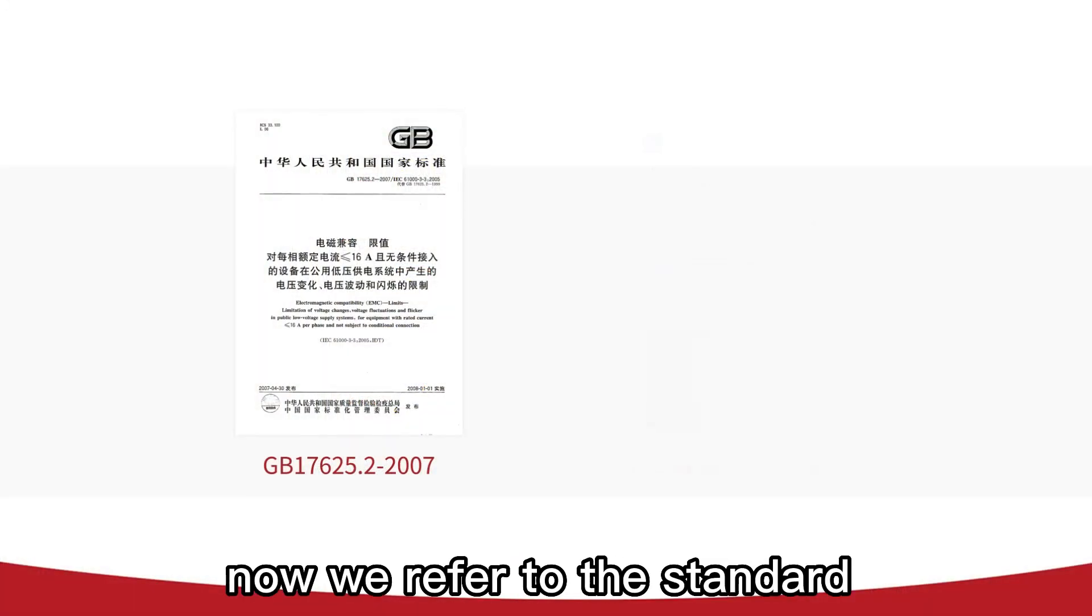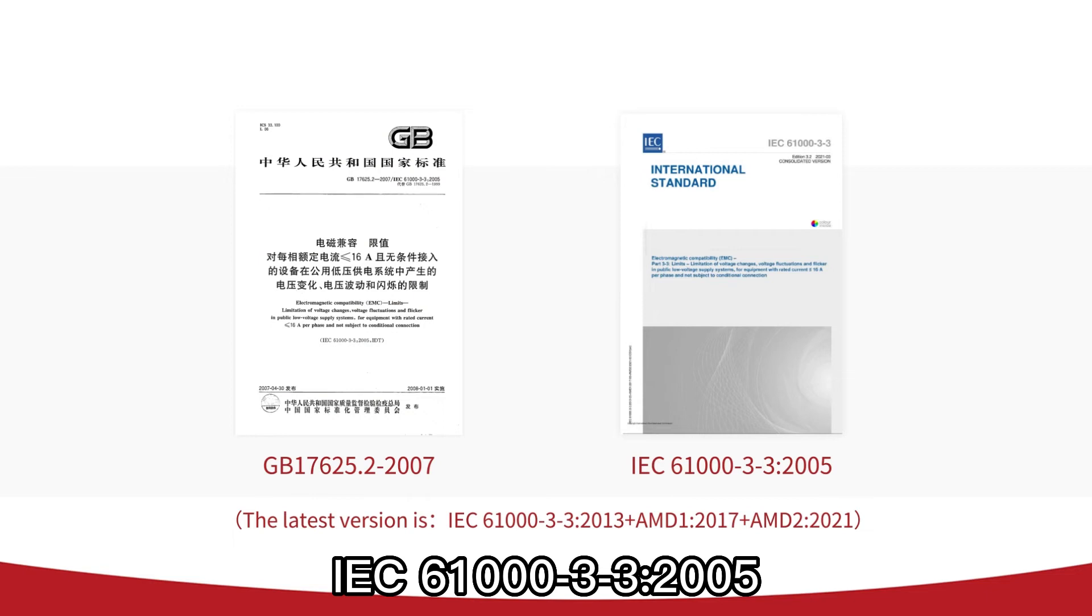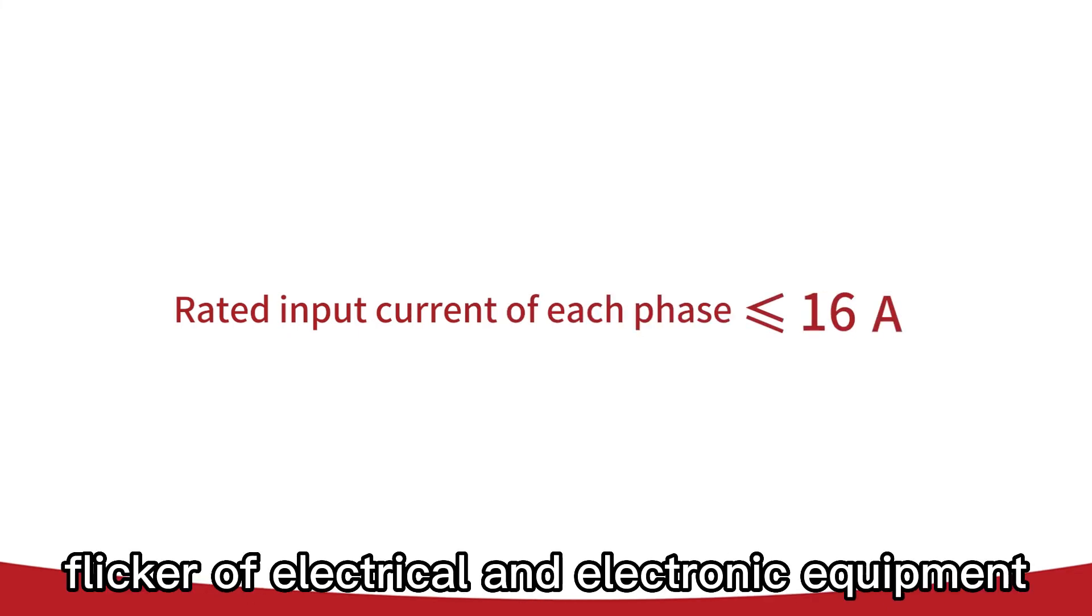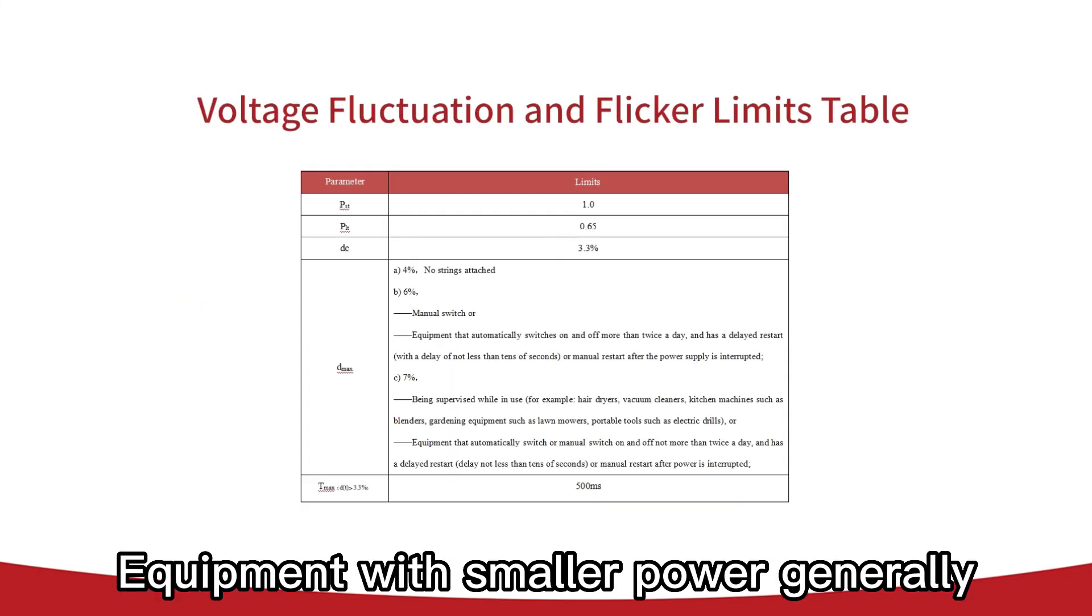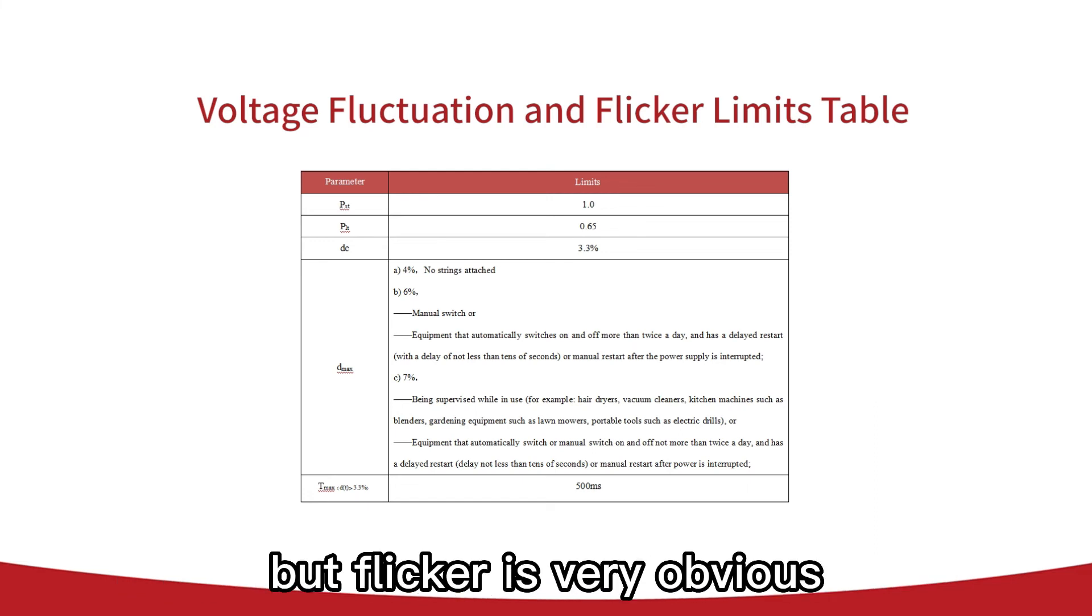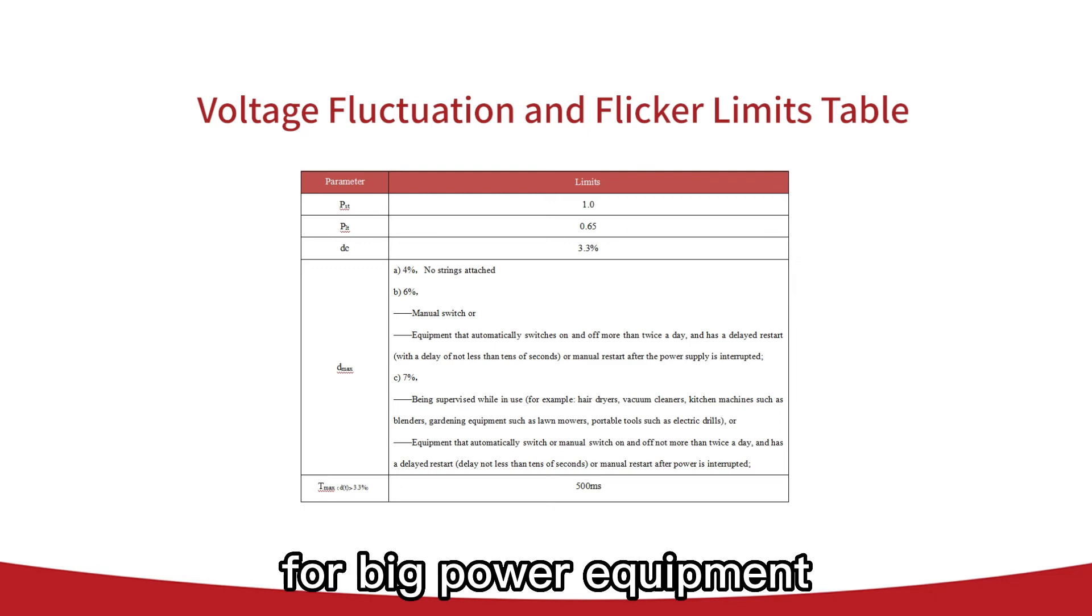In China, we refer to the standard IEC 61000-3-3-2005. The standard sets the limitation about the voltage fluctuation and flicker of electrical and electronic equipment with rated input current of each phase less than or equal to 16A. Equipment with smaller power generally does not cause the flicker to exceed the limitation, but flicker is very obvious for big power equipment.